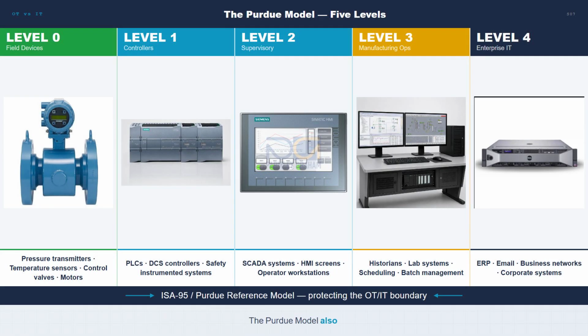The Purdue Model, also called the ISA 95 model, shows how IT and OT are organized into 5 levels inside a plant. At the bottom, Level 0 contains the field devices, your pressure transmitters, temperature sensors, control valves, and motors. These interact directly with the physical process. Level 1 is the control layer, PLCs and DCS controllers that execute control loops and safety functions. Level 2 is the supervisory layer, SCADA systems and HMI screens that display process information.